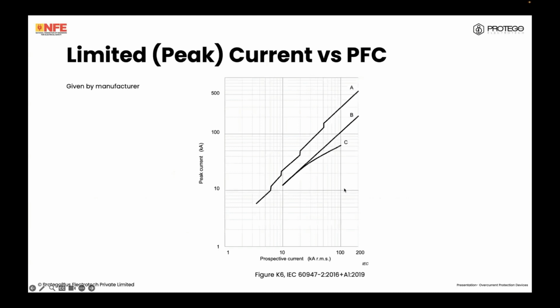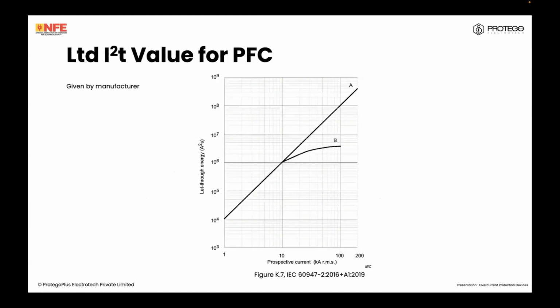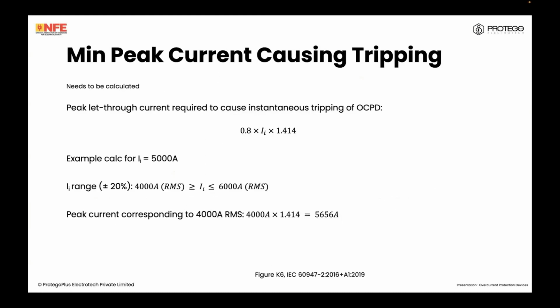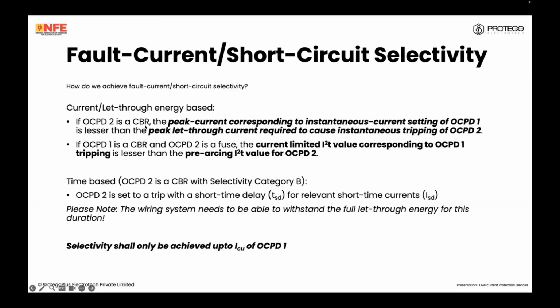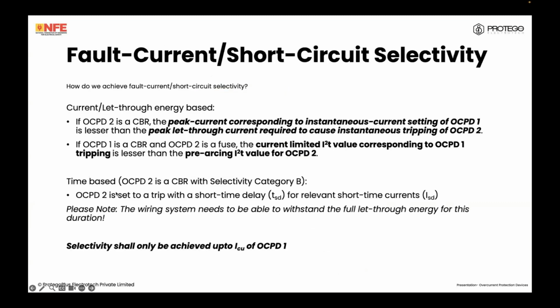Obviously, this is a lot more complicated process. So very often the manufacturer will give you a table. Now this is for OCPD of circuit breaker, or if you have a fuse, basically, the current limited I square T value corresponding to OCPD1 shall be lesser than the pre-arcing value. So how much I square T will this release when it trips, and how much I square T will this have just before it blows?